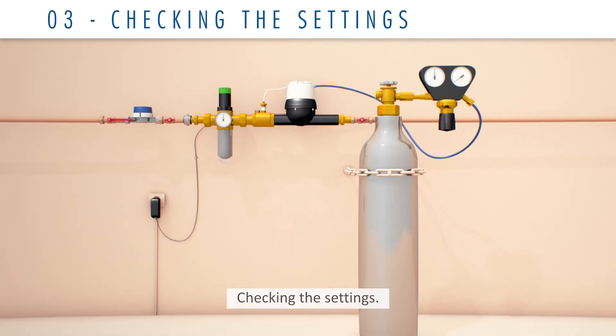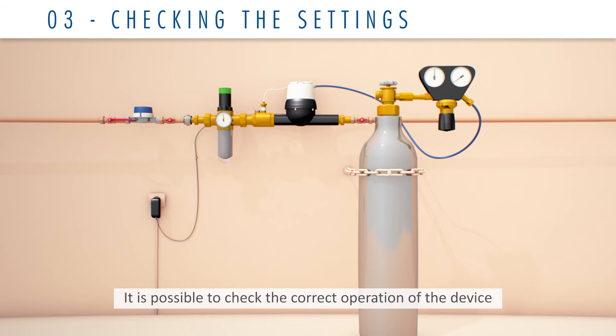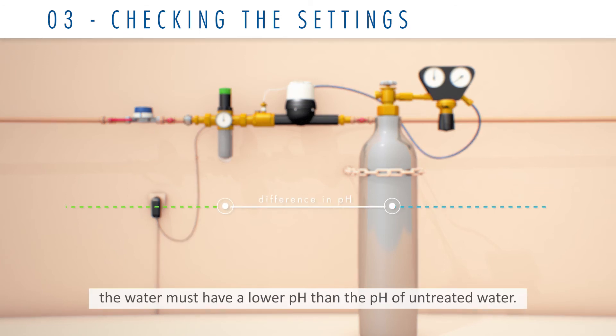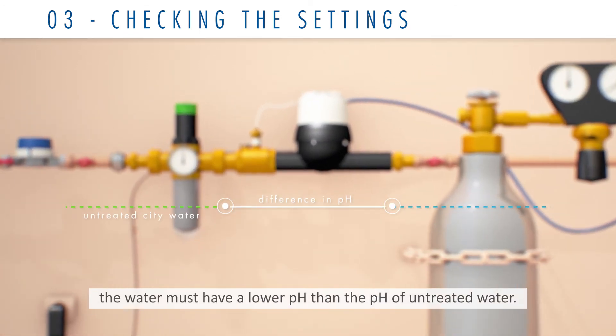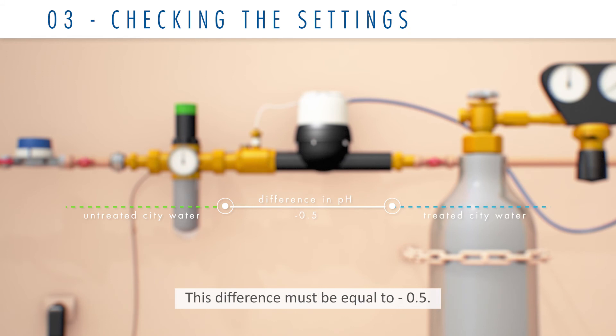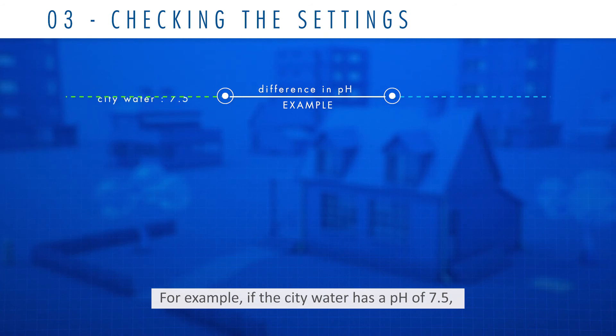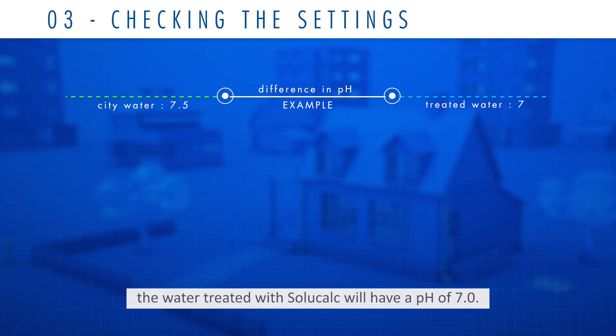Checking the settings: it's possible to check the correct operation of the device by measuring the difference in pH before and after the SoluCalc. After the SoluCalc, the water must have a lower pH than the pH of the untreated water. This difference must be equal to -0.5. For example, if the city water has a pH of 7.5, the water treated with SoluCalc will have a pH of 7.0.